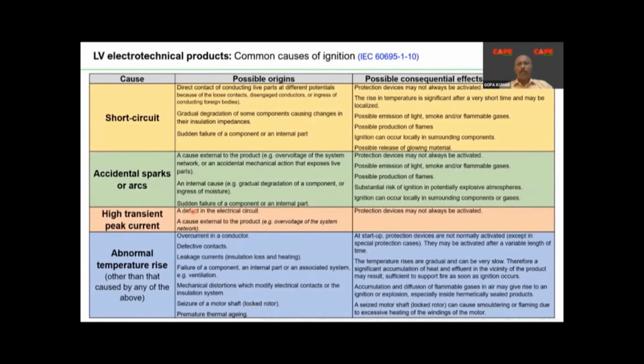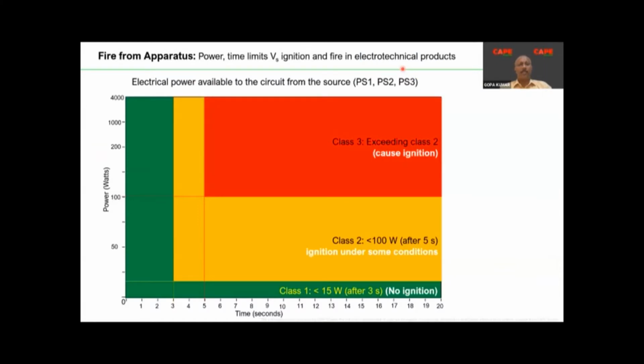With respect to the creation of fire, there are 4 sources identified and considered in the IEC standards, based on several research and actual study reports. One is the short circuit, then accidental sparks, high transient peak current, and abnormal temperature rise. Each cause is attributed to possible origins, and the possible consequences are also evaluated very well. These consequences are converted into possible design of an electrical apparatus and finally testing of an electrical apparatus. I'm just showing you a standard, IEC 60695-1-10. This series of standards consists of 37 standards, which talk about different kinds of testing in electrical apparatus.